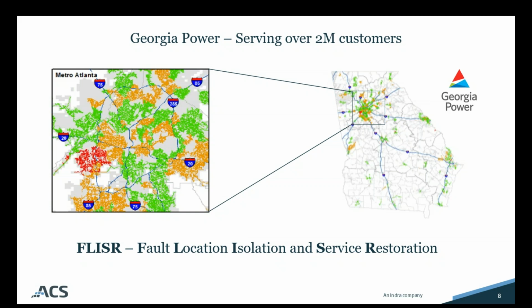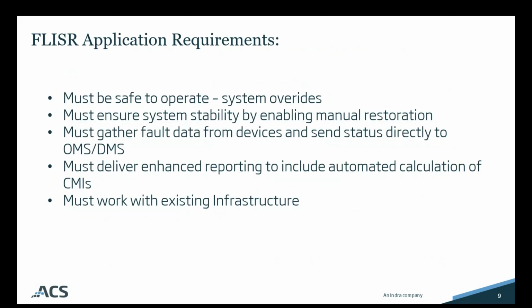So the solution requirements: the system must be safe to operate with system overrides. It must ensure system stability by enabling manual restoration. The system must gather fault data from devices and send status directly to an OMS or DMS. It must deliver enhanced reporting to include automated calculations of CMIs, and that would be customer minutes interrupted. And importantly as well, it must work with existing infrastructure.